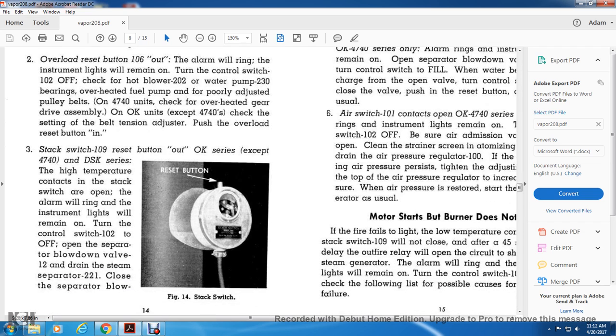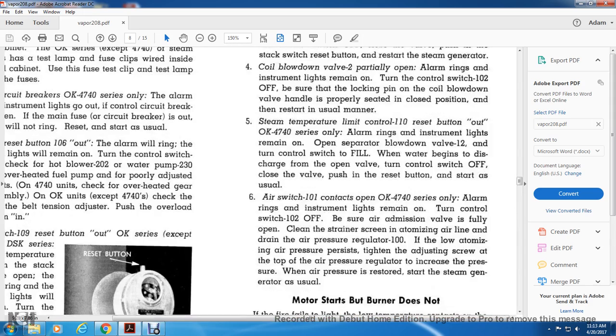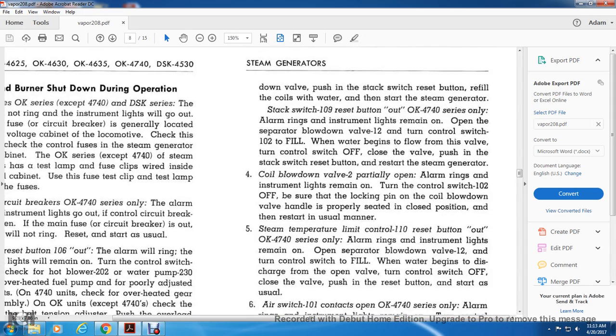3. Stack switch 109 reset button out with the OK series, except for the 4740 and the DSK series. The high temperature contacts of the stack switch are open. The alarm will ring and the instrument light will remain on. Turn the control switch 102 to the off. Open the separator blowdown valve 12. Drain the steam separator 221. Close the separator blowdown valve. Figure 14 shows the stack switch and the reset button. Push the stack switch in with the reset button, refill the coils with water, then start the steam generator with the stack switch 109 reset button in, OK for OK.